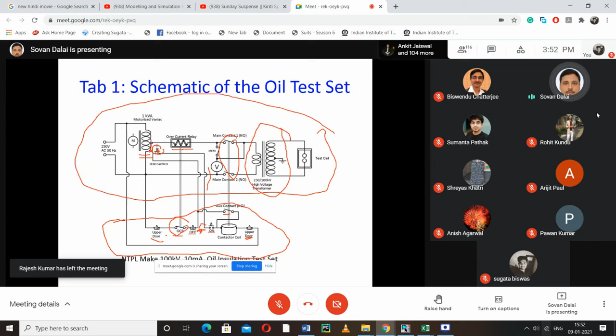And this is the photograph of the oil test setup. This is the NTPL make high voltage oil test set, and we can generate a maximum of 100 kV. This is the standard cell, which contains 300 ml of oil. Already sir mentioned that the electrodes have a 12.5 millimeter diameter, and you have to maintain a gap distance between the two electrodes of 2.5 millimeter.